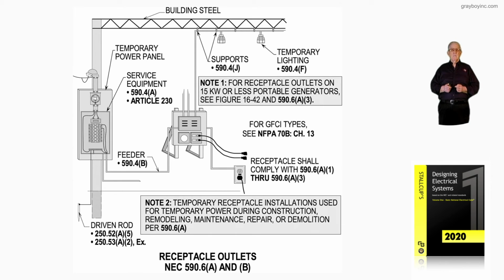And then notice that we could use non-metallic sheath cable, Romex or rope, again, depending on what part of the country you are from. But notice there's no 3-story limitation on that for temporary construction. We're using wiring methods less than would be required if these installations were permanent.